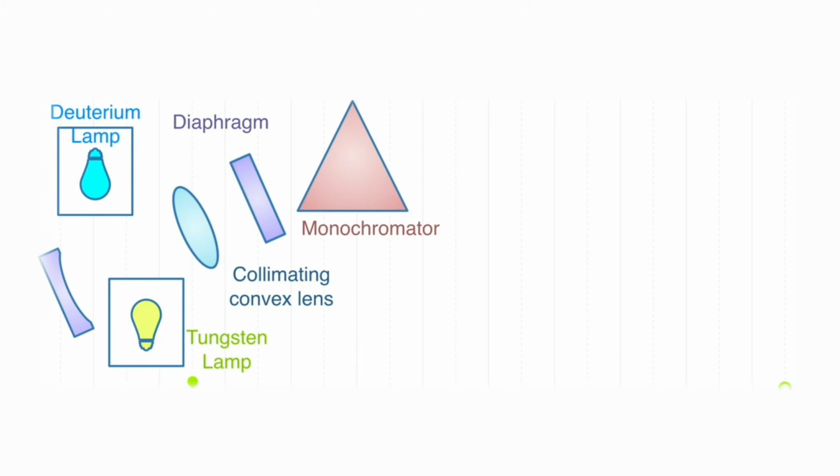Then there is a monochromator. Monochromator is used to obtain the radiation of one wavelength. The monochromators may be a prism or diffraction grating. The instrument whose demonstration will be shown in today's session is a JASCO V630 spectrophotometer, which is provided with a concave grating functioning as monochromator.